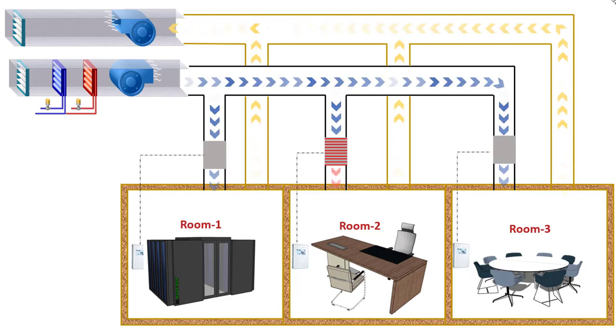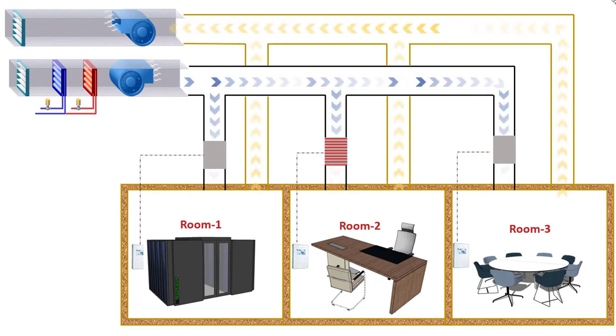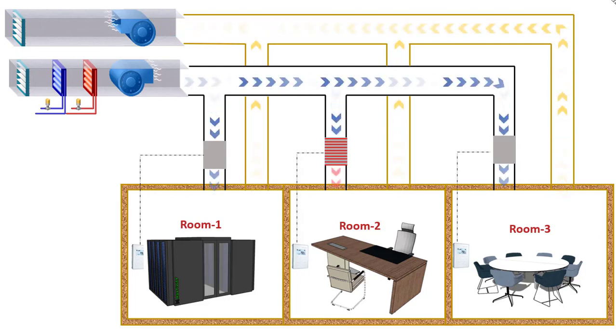Sometimes a bypass damper can also be used inside a terminal unit along with the duct heater. When less cooling is required, then this bypass damper is partially closed and bypass some portion of the supplied air into the ceiling plenum where it is added to the return air. So in this way, less air is supplied to the room, resulting in less cooling. But this bypass damper cannot be fully closed due to the ventilation requirements. Usually minimum of 30% damper shall always be open. If less cooling is required, initially this damper is closed to a minimum of 30%. But if still desired temperature is not reached, then duct heaters are turned on to achieve the desired temperature.